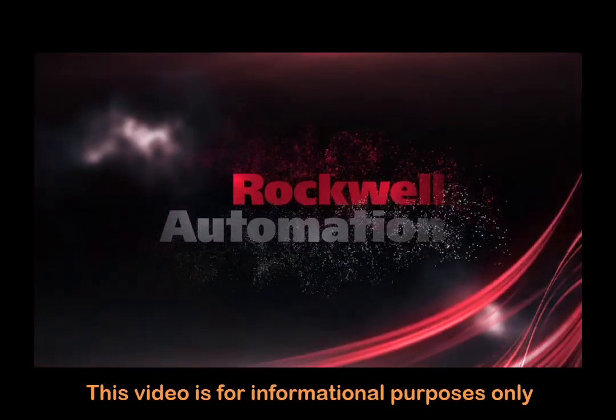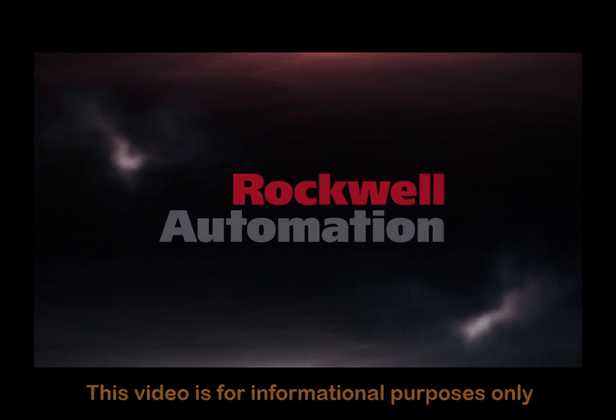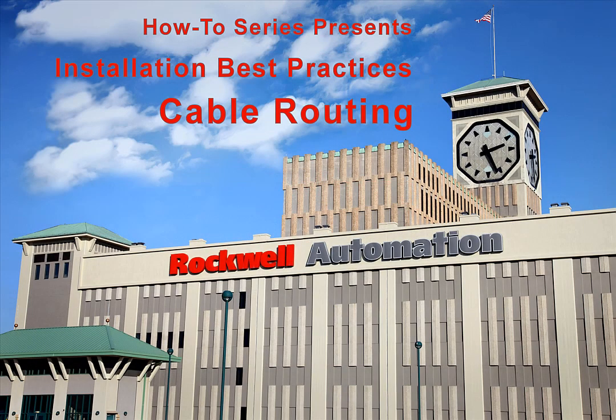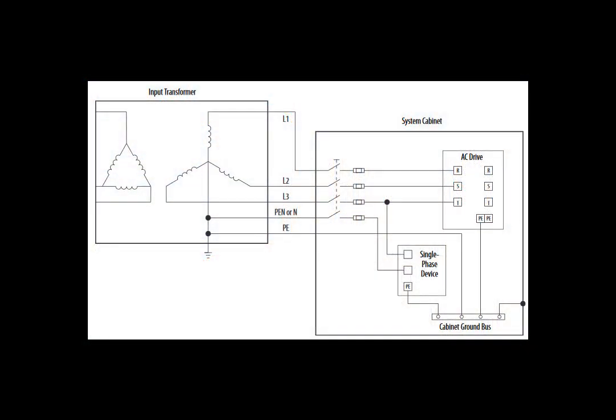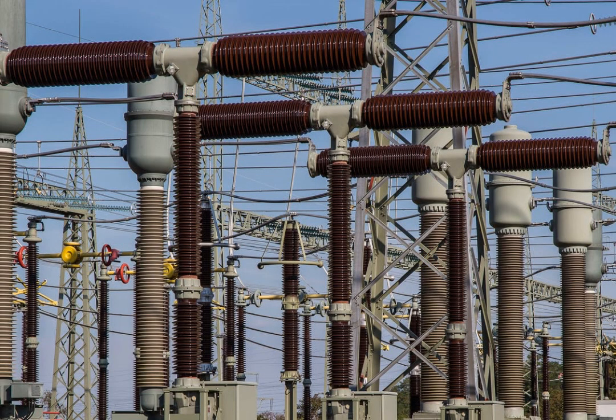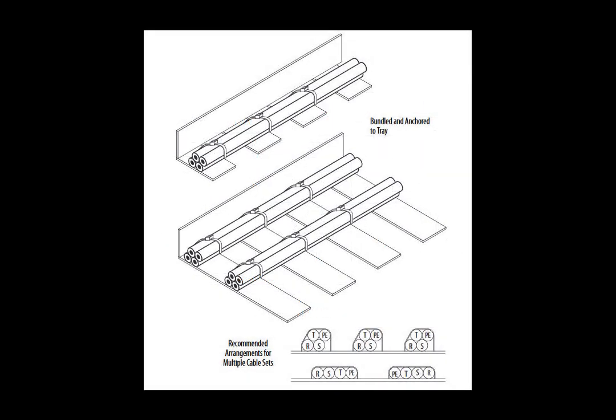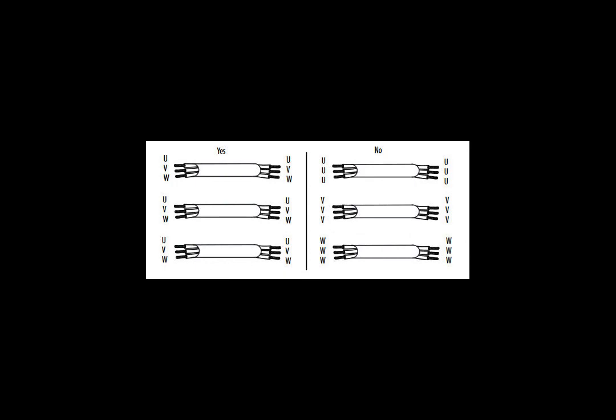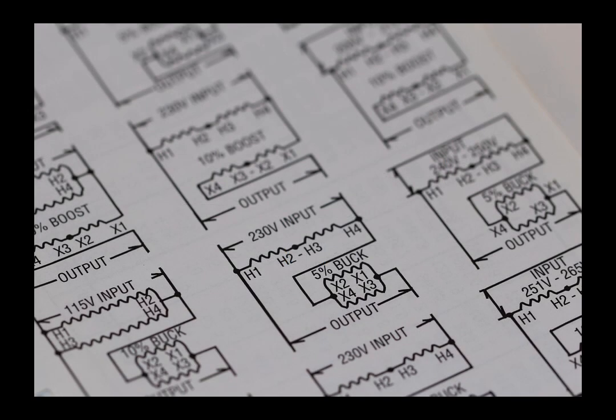Welcome. This video is part of a series of videos that focuses on cabling. This video will assist you in cable routing considerations when planning cabinet layout and cabinet routing of a drive system. One of the more challenging issues to troubleshoot in an electrical system are associated with voltages and currents coupling from one wire to another. Unpredictable control behavior can occur on an electrical system that has poor cable isolation. Taking steps to minimize noise coupling from one electrical system to another at the design phase can greatly reduce or eliminate problems in the future.